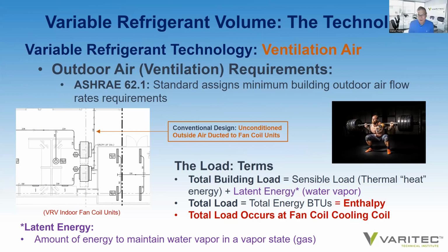most local code authorities. So in looking at this type of system, let's look at the variable refrigerant indoor air handler component. If you're bringing untempered outside air and ducting it into a VRV plenum, so you get outside air distributed throughout a building, the total load of that building, including the building load and the outside air load, is seen at the cooling coils of the air handler of the VRV system.